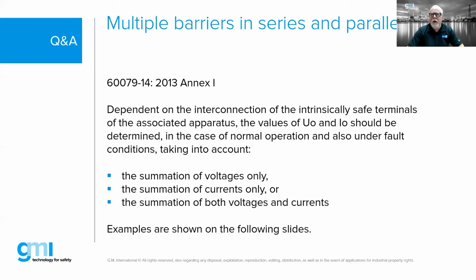Yeah, this comes up every now and then. So where do we find this information? It's in the 60079-14 standard, the design and installation standard. It's in the IEC version, it's in the EN version, it's all over the place. We need to take into account, on the associated apparatus, the values of capacitance, inductance, and power, so we can do summation of voltages, summation of currents, or summation of both voltages and currents.